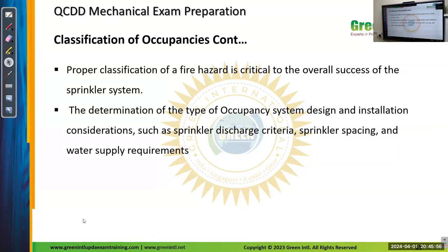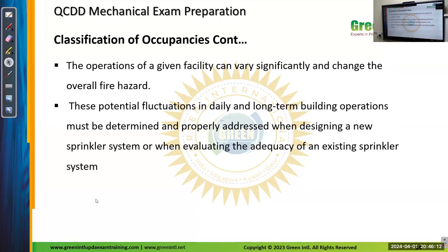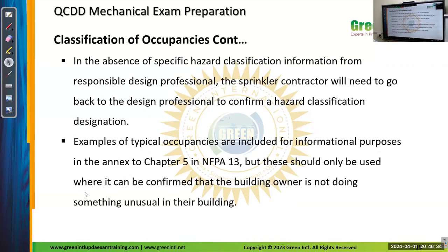So proper classification of a fire hazard is critical to the overall success of the sprinkler systems. Determination of the type of occupancy drives system design and installation considerations such as sprinkler discharge criteria, sprinkler spacing, and water supply requirements. Operation of a given facility can vary significantly and change the overall fire hazard. The potential fluctuation in daily and long-term building operations must be determined and properly addressed when designing a new sprinkler system or when evaluating the adequacy of existing sprinkler systems. This is the explanation for why we are classifying for these sprinkler systems.